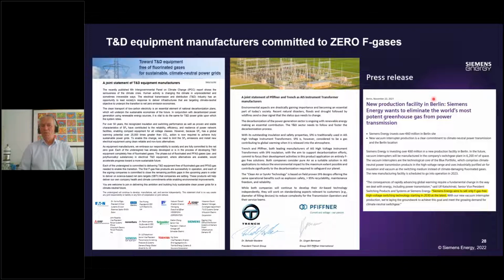And on the right-hand side, you see the press release of Siemens Energy, who state that Siemens Energy goes for vacuum and clean air technology, so greenhouse gas free technology, and the aim is to sell only F-gas free high voltage switching technology starting in 2030. This is in 8 years. So we are in the middle of the transformation of the SF6 portfolio into the greenhouse gas free portfolio. To realize that, Siemens Energy is building a new factory for high voltage vacuum interrupters in Berlin. It started last year, and it will go into operation in 2023, next year.